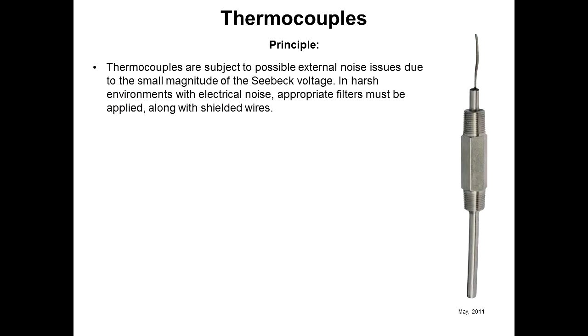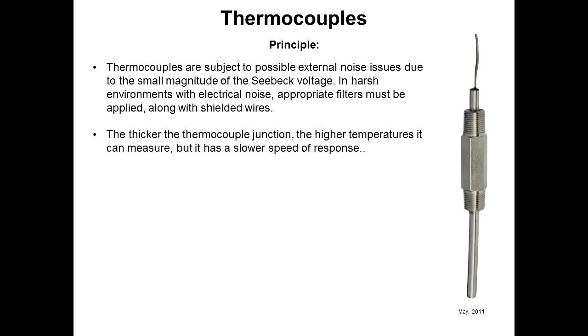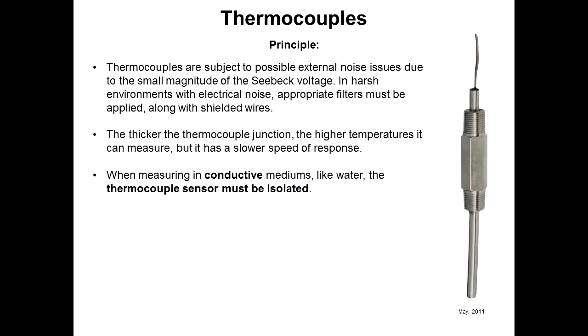So thermocouples are subject to possible external noise issues due to the small magnitude of the Seebeck voltage. In harsh environments with a lot of electrical noise around, appropriate filters must be applied along with shielded wires. The thicker the thermocouple junction, where the two wires are connected, the higher temperatures it can measure, but it will also have a slower speed of response. When measured in conductive mediums like water, the thermocouple sensor must be isolated. You can't use a bare junction thermocouple in a conductive liquid.